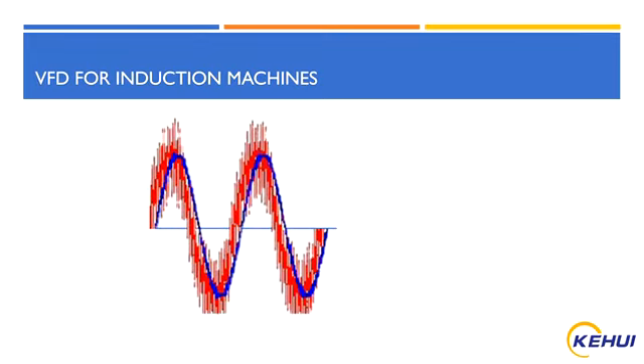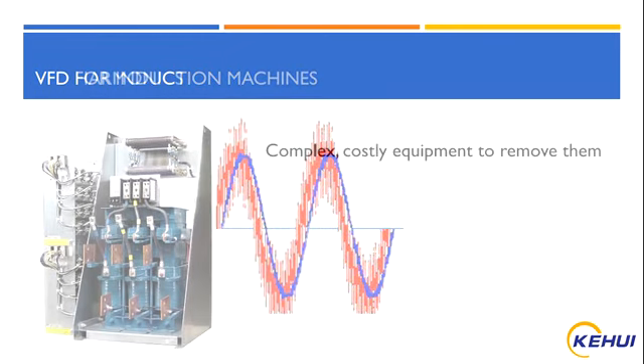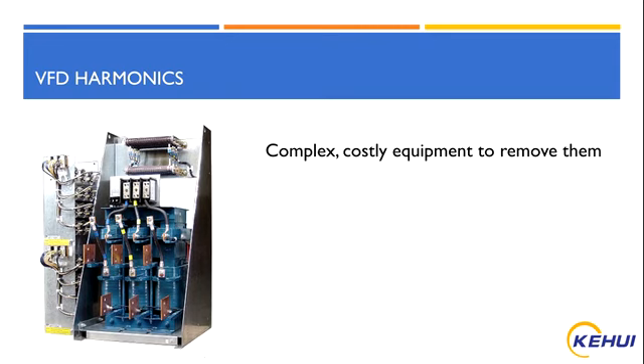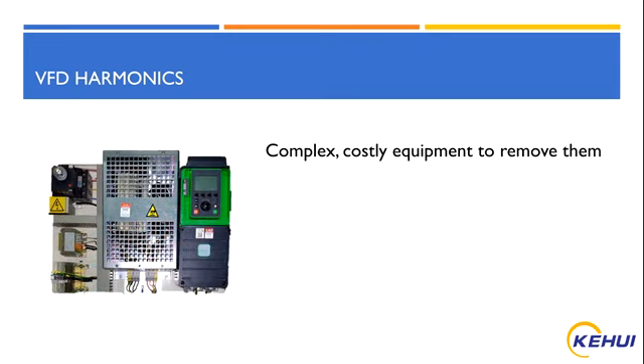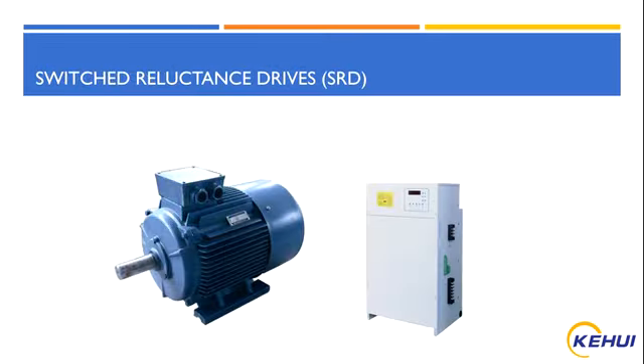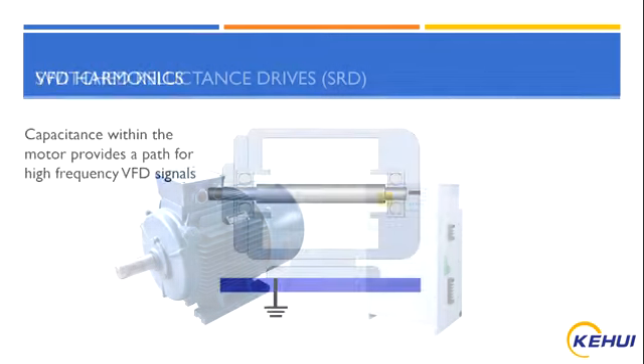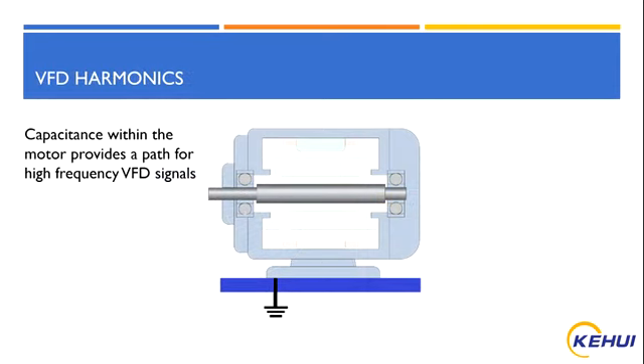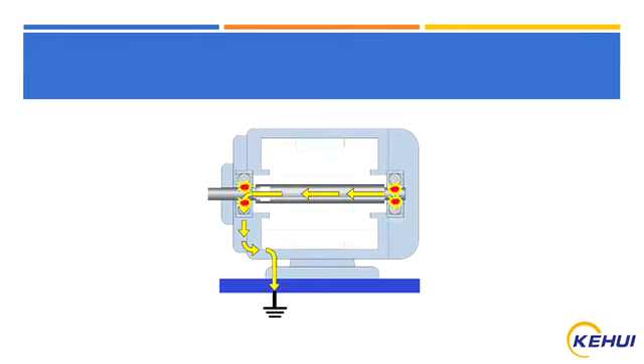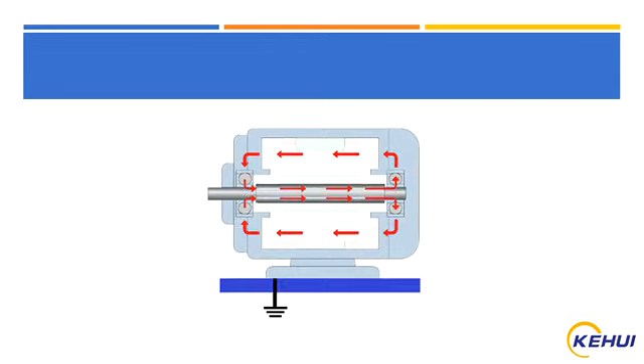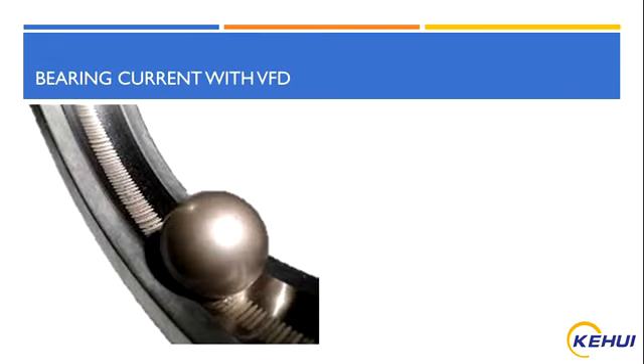The unwelcome effect on the power quality of the system may have to be dealt with by installing complex and costly equipment to remove the harmonics. In some cases, power company rules might make this compulsory. The absence of high frequencies on switch reluctance machines makes such equipment unnecessary. Another problem which may be encountered is that capacitance within the motor may provide a path for the high frequency signals. As a result, current may flow through the bearings to the earth. This phenomenon, which is known as bearing current, can result in pitting in the ball race, which in turn affects the efficiency of the machine.